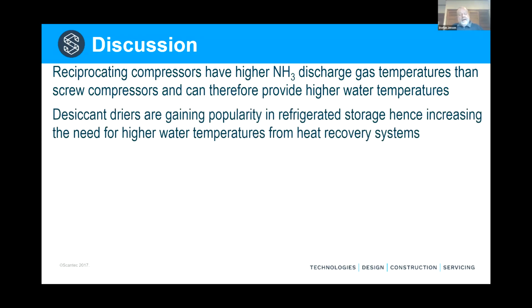Desiccant dryers are gaining popularity for a whole bunch of reasons. The main reason being the prevention of slippery floors. Other reasons are extending the defrost intervals so that we have more hours between each defrost. Improvement in product quality. We don't have any frost settling down on the product, and quite often the product is barcoded. Frost on the product prevents you from reading the barcode. And large-scale ASRS systems, automatic storage and retrieval systems for boxes, the meat in cartons and the like, they require dew points that are sometimes below -30, because otherwise their automatic retrieval systems simply do not work. So this is an application that's coming more and more.